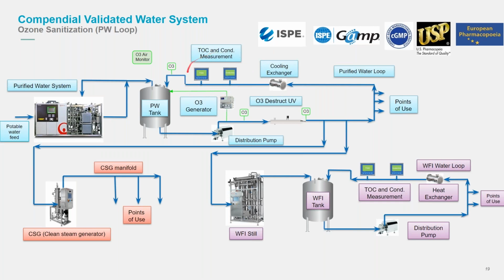We have our critical instruments on the return line to measure TOC and conductivity, and we have a sample valve on the return hygiene sample valve to take away and do your microbial testing on that basis. So, typical purified water system.